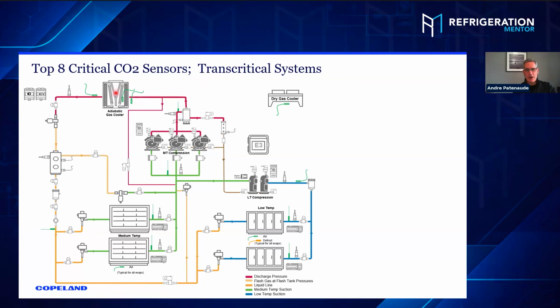But you'll notice on here, I've got a couple of sensors, and I'll talk more about those. My gas cooler out, my pressure transducer in the drop leg, my high pressure control and valve driver, high pressure valves. Another sensor here is my flash tank sensor, high level, low level receiver flash tank sensors. I've got my bypass valve. Flash tank goes to my medium temp cases, to my low temp cases, and you'll notice I also have my pressure transducer, temperature sensor, and case controls on each, which are typical. So I didn't put sensors everywhere, but just for one, which is typical.